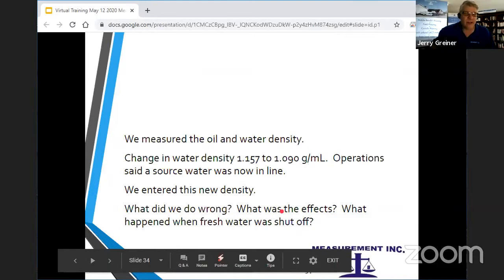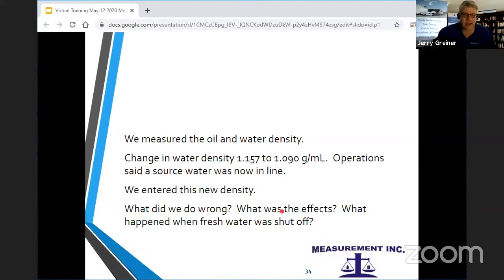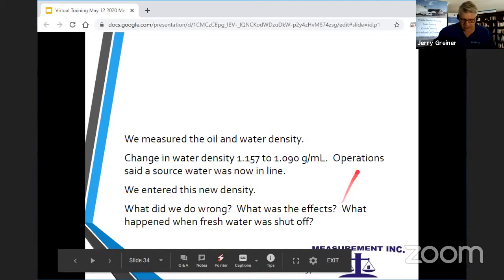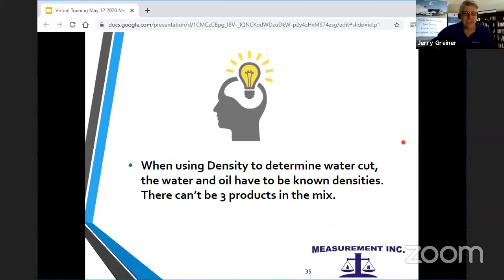It was perfect when we were there. It had the exact water cut. We tested the water cut. But as soon as there was any change in the fresh water going in with the produced water, it didn't work. And what we learned is when you're using density to determine water cut, you can have water and oil, and they need known densities. If you have 3 products like fresh water, produced water, and oil, you don't know what that water density is. And so you really don't know your final density. So if you're using density, you have to have 2 products and know the densities. So we learned something from that as well.